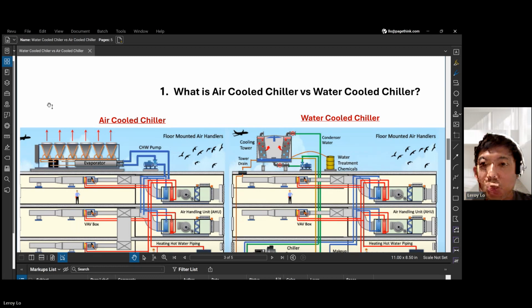so it's on the right. In contrast, if we were to do a water-cooled chiller for this building, it would need so much space. Now we have to get rid of the air-cooled chillers, and then open up a room dedicated in the first floor, preferably, and install a chiller and a pump in the first floor, normally in a dedicated room for that. And we will need to provide access louvers or access to replace these chillers. As you can see on the first floor on the right side, if we ever have to do some replacement, to clean the pipes, replace the pipes, we will also need to install the chilled water pipes for those.